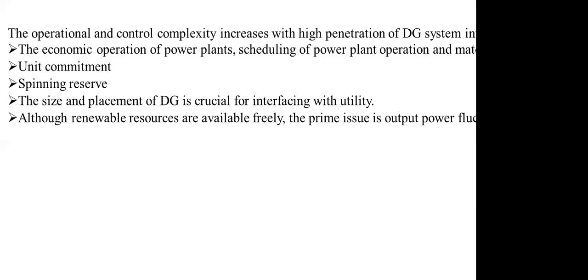One of the major issues is that size and placement of DG plays a very crucial part in the operation of the power grid, because if you don't size it properly, the point of common coupling may lead to voltage sag, and all sorts of issues will come. If you connect at a very high voltage end, it will lead to a very large voltage spike. If you connect at a very low voltage end, that also becomes a problem.